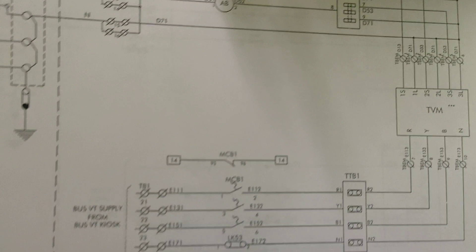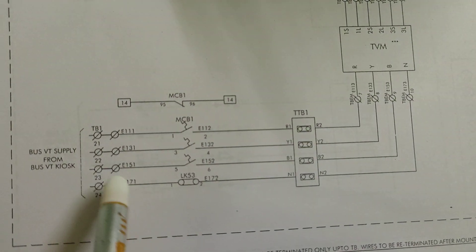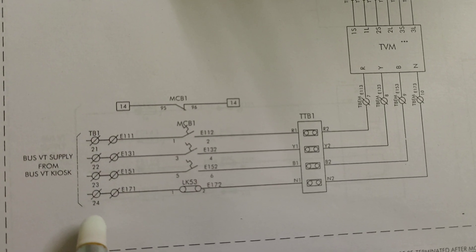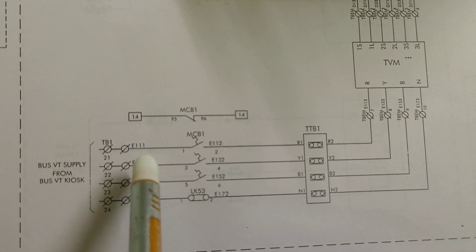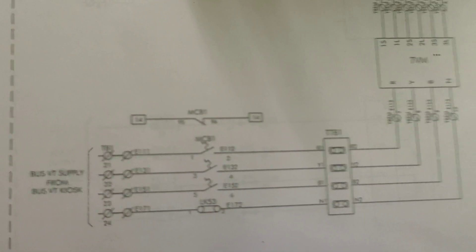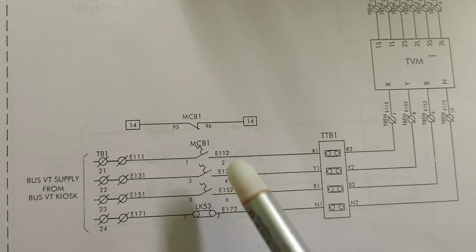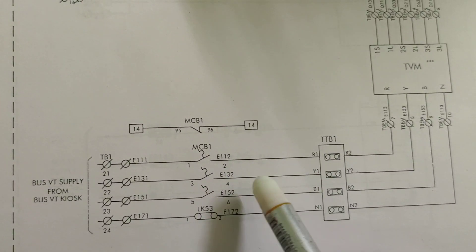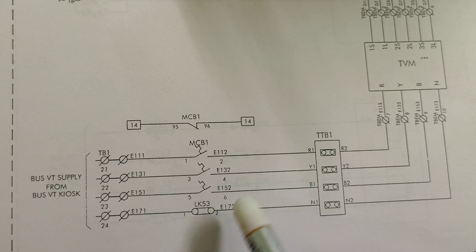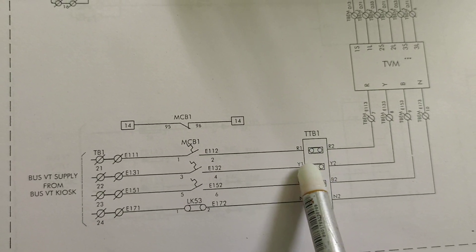The TVM is the tri-vector meter. One side of the TVM connection comes from the VT — voltage transformers. From the VT, four wires come out: E111, E131, E151, and E171. An MCB (MCB1) is used before the TTB1. After the MCB, the ferrule numbers become E112, E132, E152, and E172. This connection goes to the TTB1 with terminals R1, Y1, B1, and N1, converting to R2, Y2, B2, and N2.